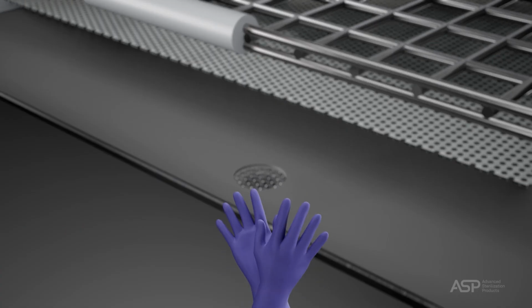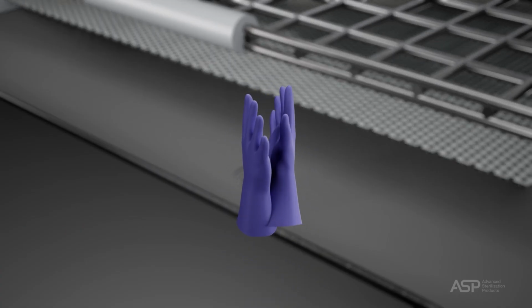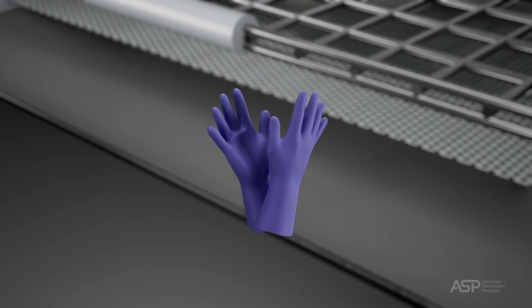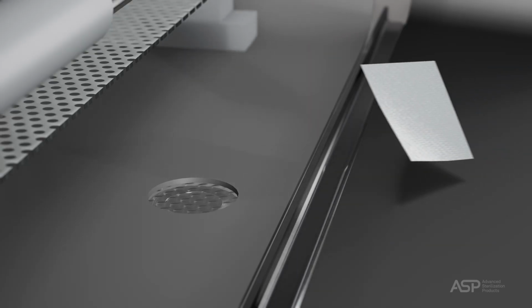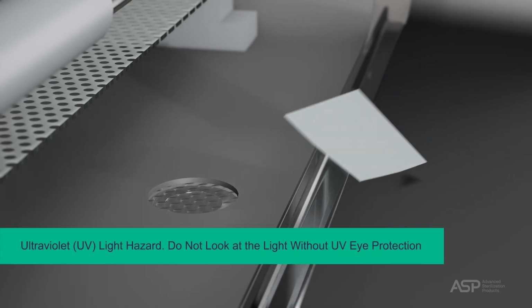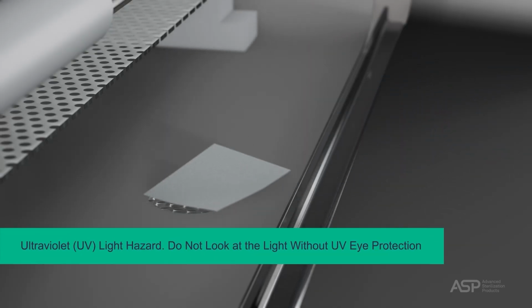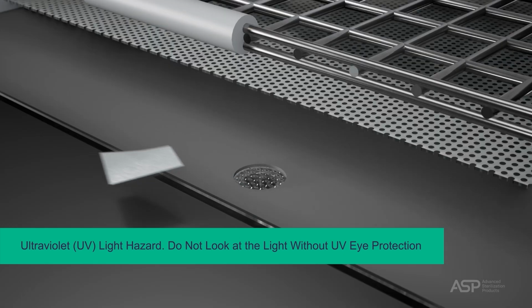To clean the lens, first put on chemical-resistant latex, PVC vinyl, or nitrile gloves. Then moisten a lint-free cloth with isopropyl alcohol and wipe the lens to remove any accumulated debris. Never use an abrasive cleanser.